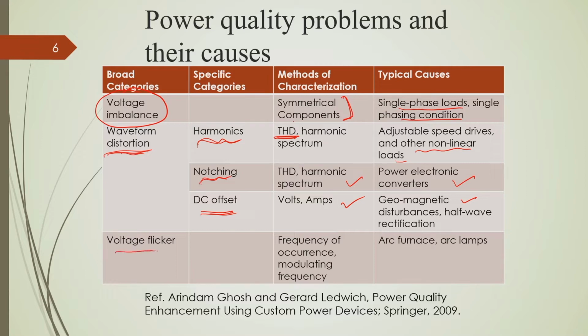Similarly, voltage flicker is also a sudden change of the supply voltage, which causes a sensation in our eyes. So, this is called voltage flicker. If there is an arc furnace type of load or arc lamps used in some locality, this will cause this kind of voltage or power quality disturbance nearby. It is characterized by frequency of occurrence and modulation.